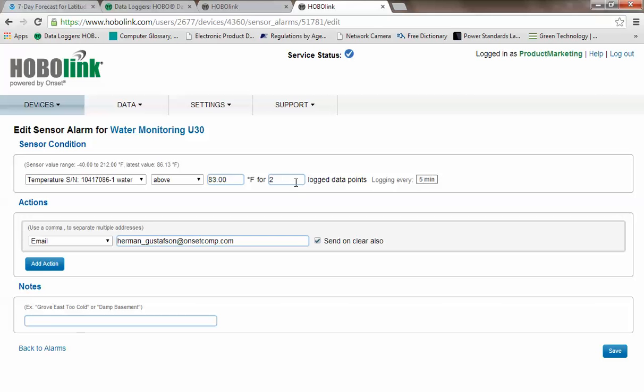We selected two log data points on this particular alarm so that we give time for the sensor to stabilize at that elevated temperature. If you want to be notified immediately, you would select one logged data point.